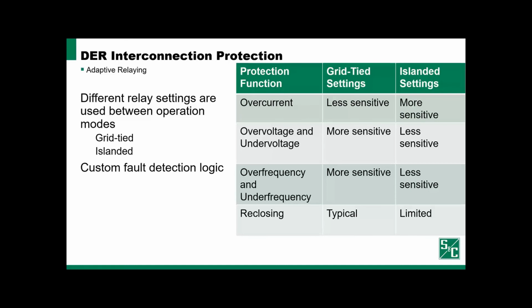Reclosing is yet another thing that changes between modes of operation. When we're grid tied, reclosing is an extremely valuable technique to improve system reliability and address temporary faults, ensuring that temporary faults aren't causing permanent outages to customers. When we're islanded, reclosing can be very stressful on the weak system with limited generation. So we often limit the reclosing that we're using when we're islanded. Some forms, such as pulse closing, which the IntelliRupter PulseCloser does, are less stressful on the system and, depending on your application, may be acceptable when islanded.